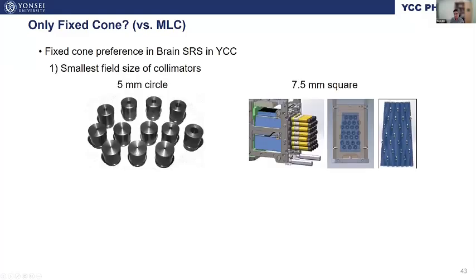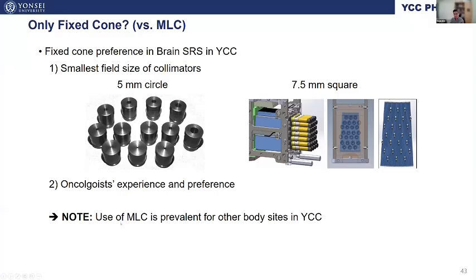Some people may wonder why fixed cones are commonly used for treating brain SRS using robotic IMRT. The key reason is associated with the smallest field size available for the collimator. Namely, a fixed cone is able to have a smaller field size than the MLC. Another reason is related to the preference of radiation oncologists. Three radiation oncologists in our department are treating brain SRS with robotic IMRT. Before the software upgrade, Monte Carlo dose calculation algorithm was available for the fixed cones only. Thus, they are used to adopting the fixed cones for treating brain SRS. But importantly, for the other body sites, the use of the MLC is predominant in our institution.